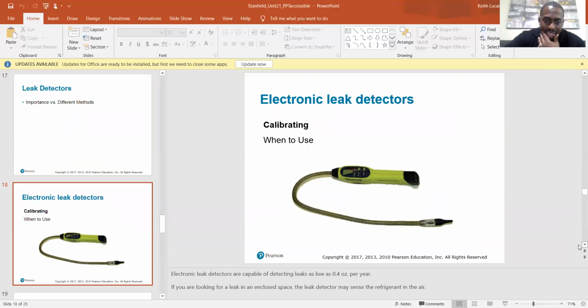So electronic leak detectors, those are pretty common. It's got this little sniffer on the end that picks up traces of refrigerant in the air. Electronic leak detectors are capable of detecting leaks as low as 0.4 ounces per year. If you are looking for a leak in an enclosed space, the leak detector may sense the refrigerant in the air. Which is why most of the time, these are hard to pinpoint the leak.